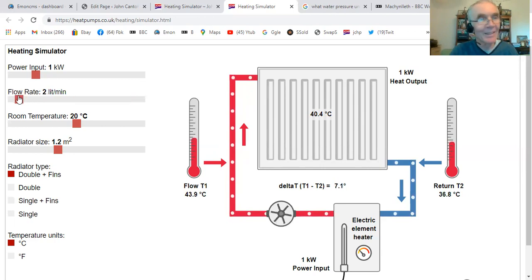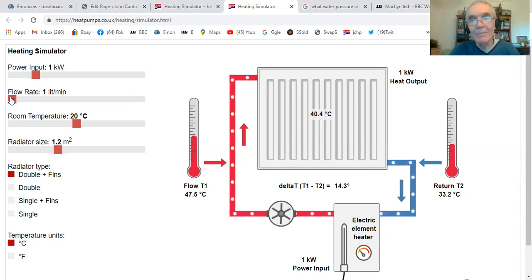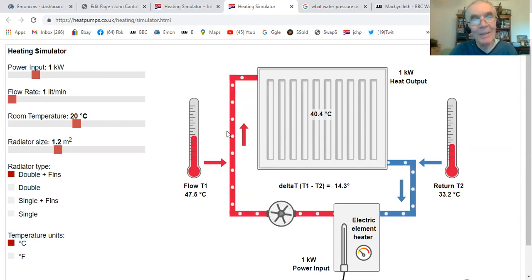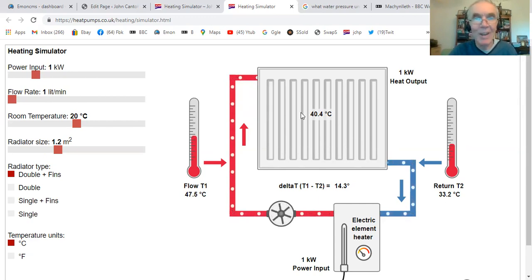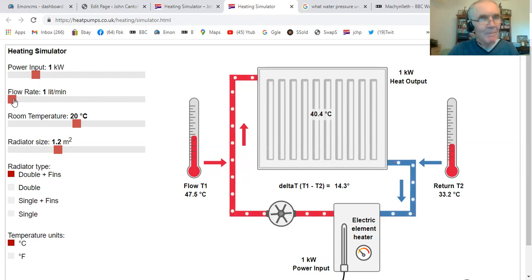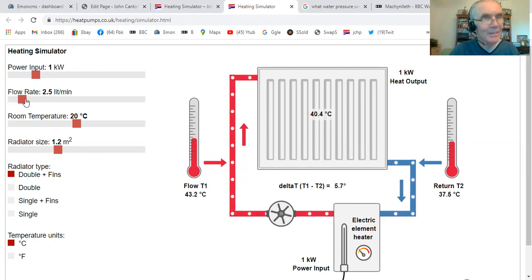Let's go to the other end of the spectrum — minimum flow. Now we're flowing very slowly. Because the water is going through very slowly, you'd expect it to rise quite a bit — we still have one kilowatt going into that water. So it's coming into the radiator at 47 degrees, cooling down as it goes across, and dropping to 33. This radiator won't be very even — we'll tend to get a lot of that hot water at one end and a dead spot elsewhere, so the radiator isn't working too evenly. But it's still giving off a kilowatt because we're putting a kilowatt into it.